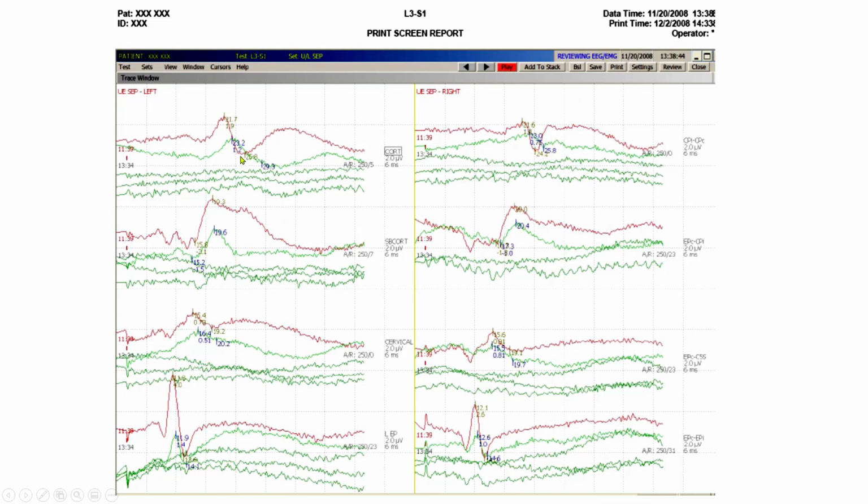And then you see these waves started fading away. Here's one run, the next run, the next run, the next run. Again, one run, the next run, the next run. It basically started going away. We push that chest piece down to where it's more over the chest and away from the brachial plexus area.